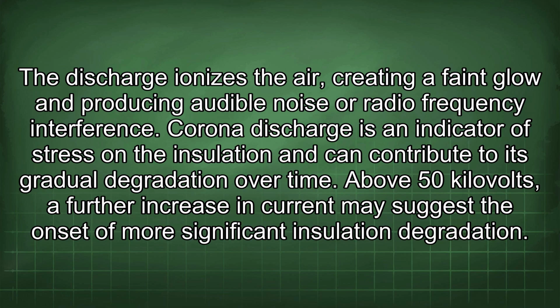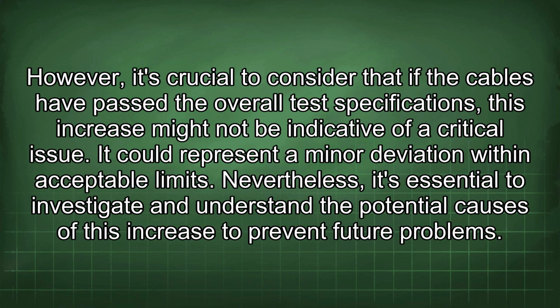Above 50 kilovolts, a further increase in current may suggest the onset of more significant insulation degradation. However, it's crucial to consider that if the cables have passed the overall test specifications, this increase might not be indicative of a critical issue. It could represent a minor deviation within acceptable limits. Nevertheless, it's essential to investigate and understand the potential causes of this increase to prevent future problems.